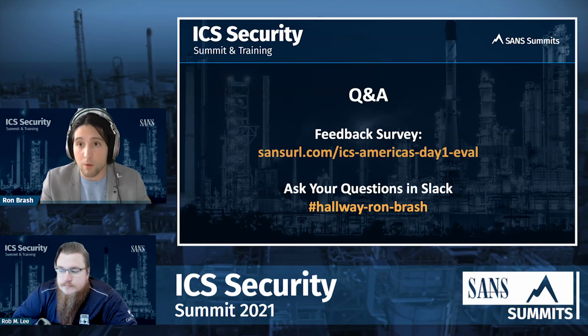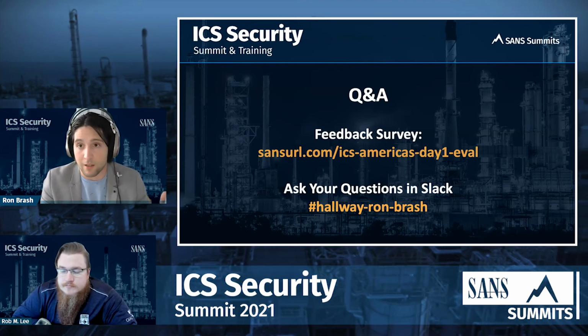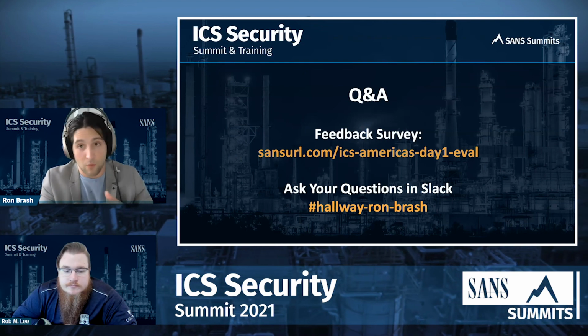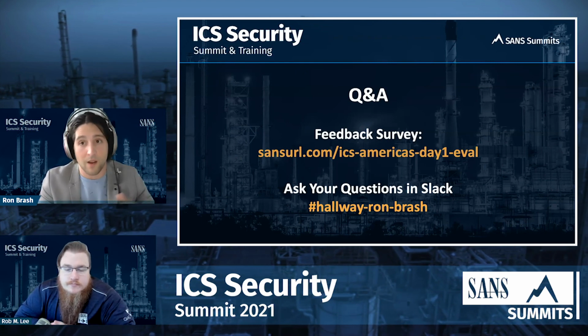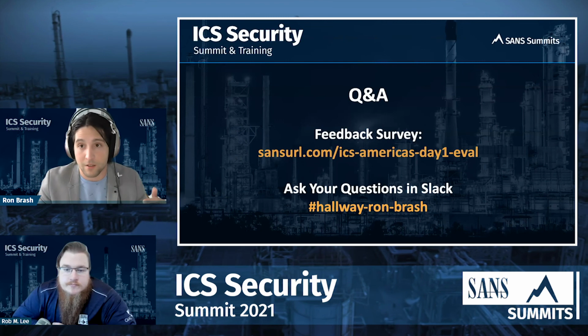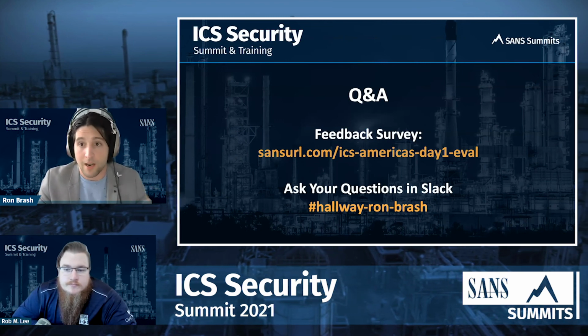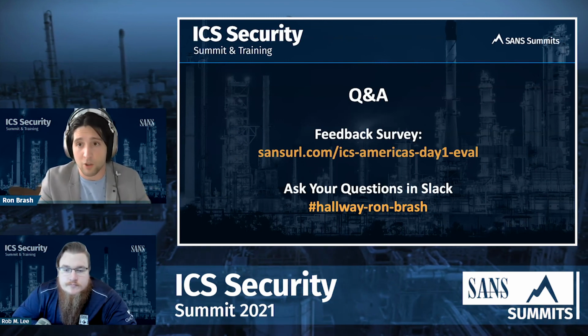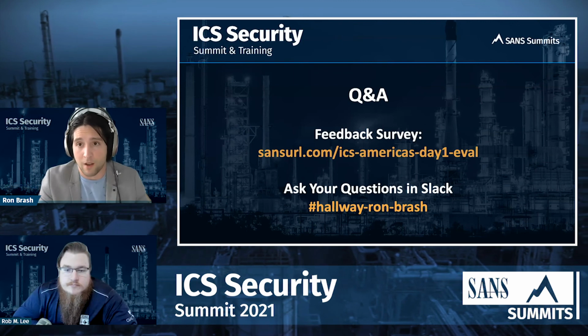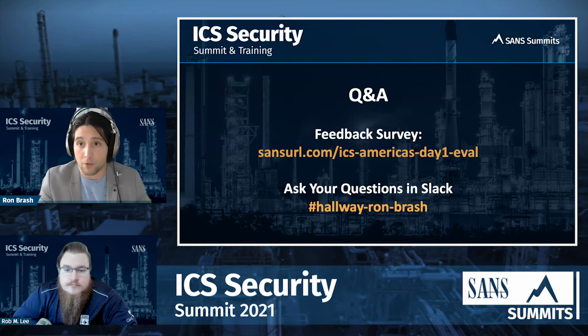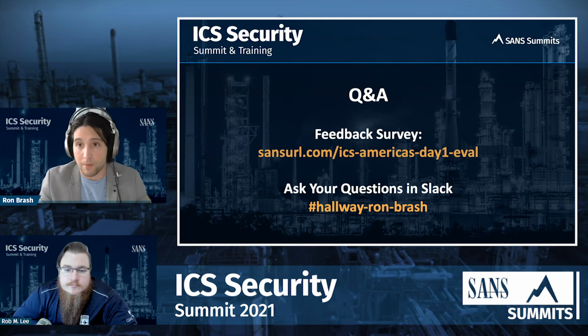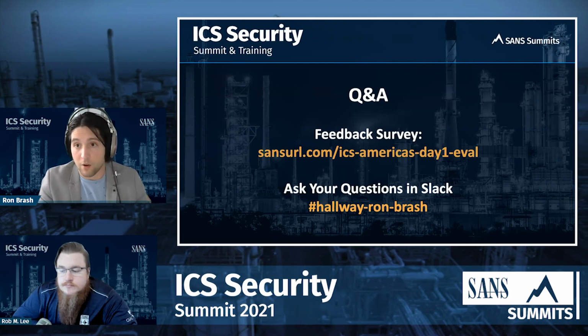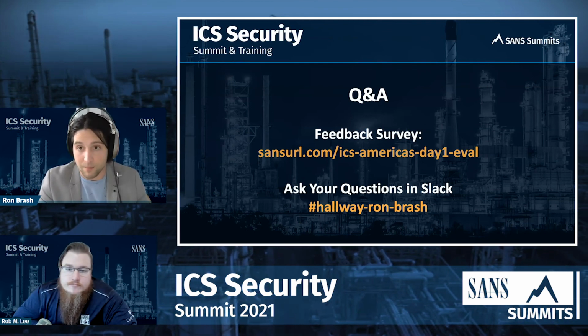So what we did for that one customer was a very small but reasonably in-depth analysis, and I looked to see if it stunk. I built an SBOM out of it. I poked at the device. I enumerated several risks, some a little more detailed than others. And I went to the CISO and said, this is what you're going to be buying into, and this is what you're going to have to inherit. I recommend you don't do it. I think you should maybe go somewhere else or use that as a stick to go hit your vendor with and get something better.